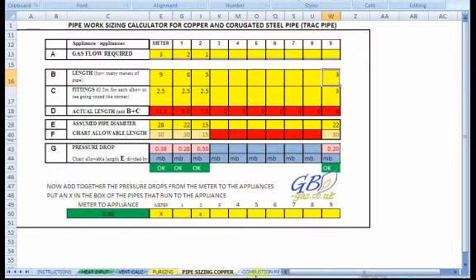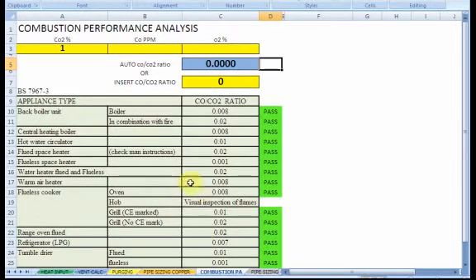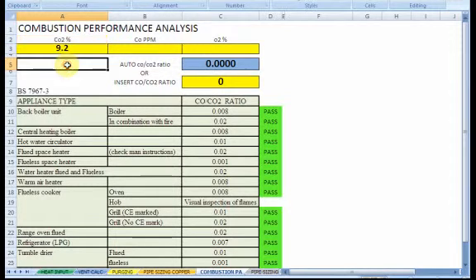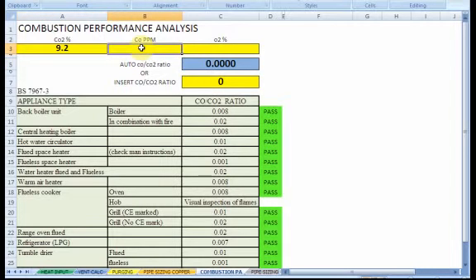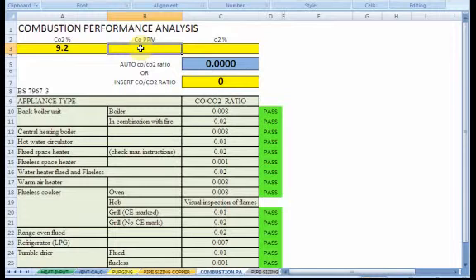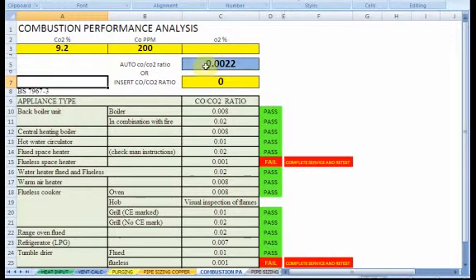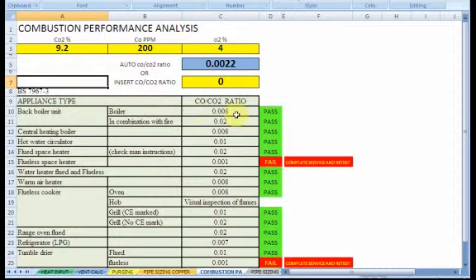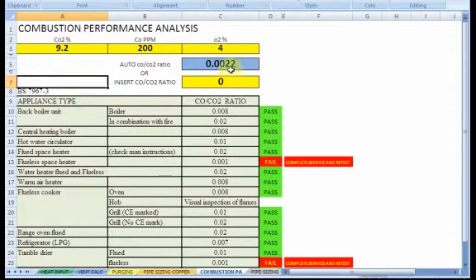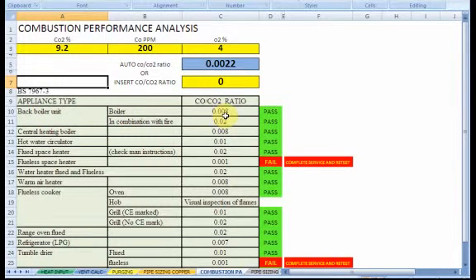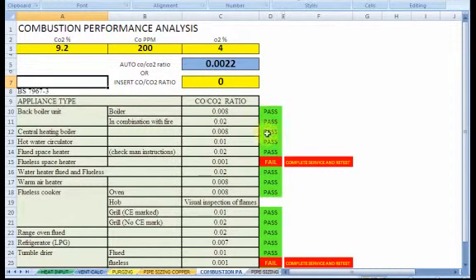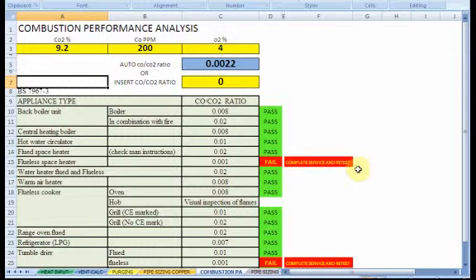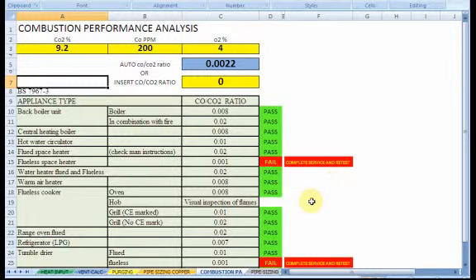That's the pipe sizing. The combustion performance analysis is pretty straightforward. Off our flue gas analyser, we'll be able to put in the CO2. Now, for a condensing boiler, you're probably looking at something in the region of 9.2 for the CO2, with the carbon monoxide being less than 250 parts per million, if it's running correctly. So, we'll say that it's 200 parts per million. The O2 content really doesn't make too much in this calculator, but you're expecting something around about 4% being left over. From there, it works out the auto-CO2 ratio, which is 0.002. And then if we check it against our boiler, 0.008 is what we're allowed. Therefore, it becomes a pass. You can see that if it does become lower, such as a flueless space heater is only allowed 0.001, it becomes a fail, and we need a complete service and retest on the appliance. And this is a nice indicator to see whether it's passed under the British standards.